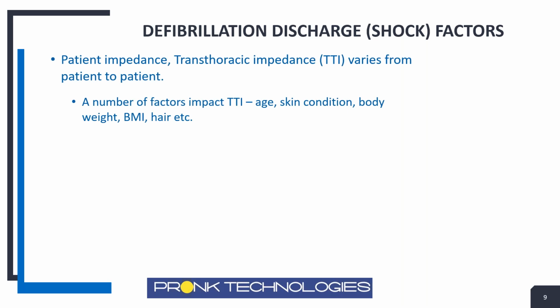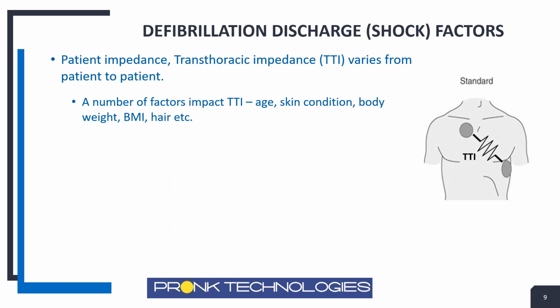One of the important features that we need to test as part of the PM or even a repair or investigate performance-wise if some incident is reported to us are the discharge tests, the shock test. And so it's important to understand that when we're doing shock testing, that the patient plays an important role in how that energy is delivered to it. And so there's a patient impedance involved, it becomes integral into the circuit, so to speak, when we're shocking the patient. And it's referred to as the patient impedance or the transthoracic impedance, the TTI value, and it varies from person to person. And it's a resistance, it's kind of a resistance that naturally occurs between 2 points.